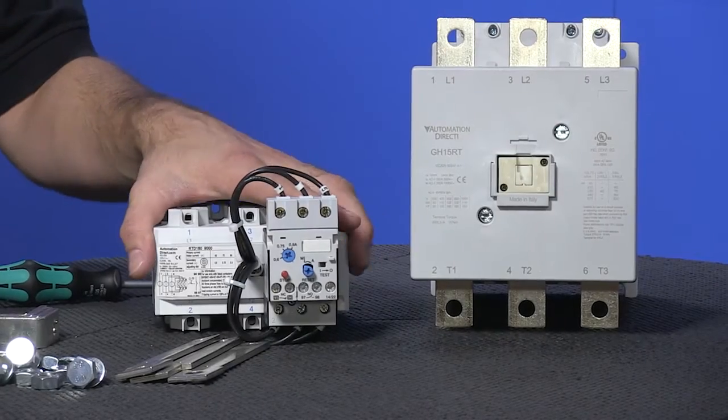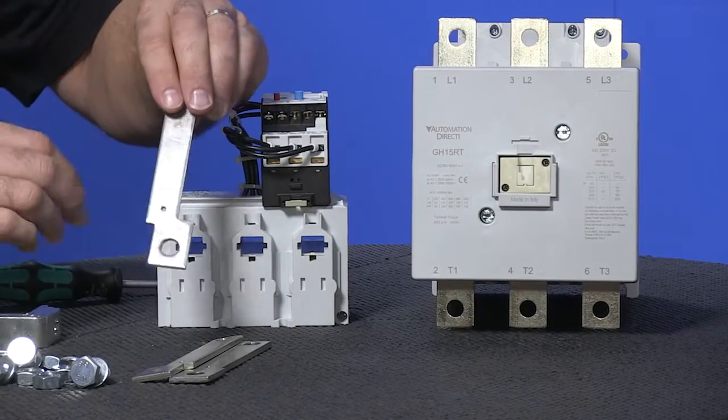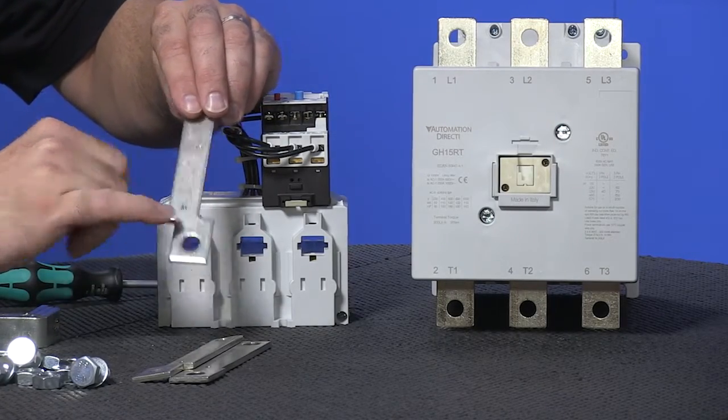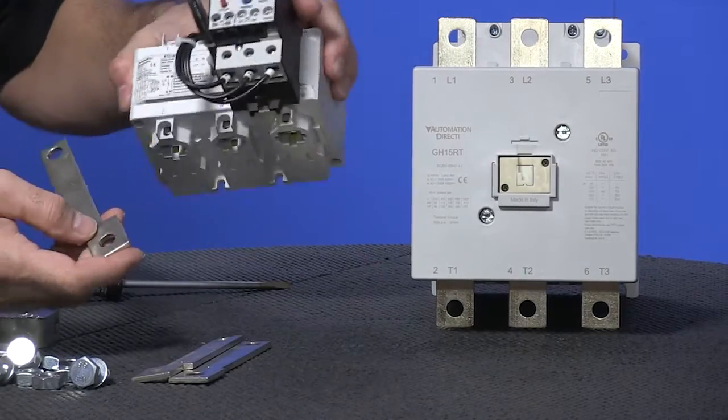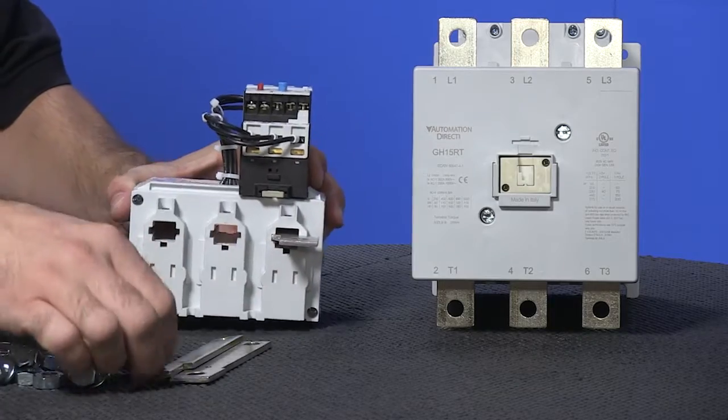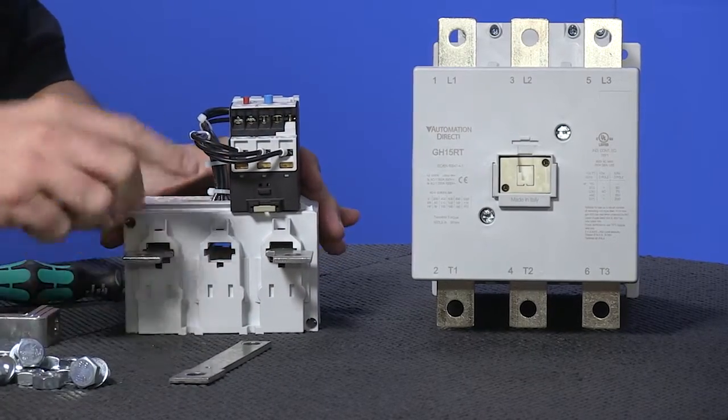First we want to slide in the included bus bars. If you look at these closely, two of them have offsets and all of them have a tapped hole. These you want to go through the bottom of the overload and the offsets need to go on the outsides furthest.